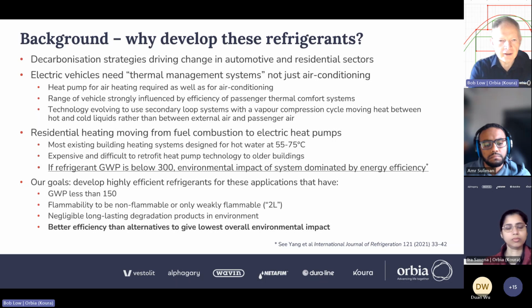So our refrigerant design goals then are really to design highly efficient refrigerants, where we're looking at GWP lower than 150. Flammability, we're focusing on non-flammable fluids. This is particularly appropriate for larger scale applications, such as some of the refrigeration type applications or building scale heat pump systems, where the constraints on using flammable refrigerants are challenging in terms of bringing refrigerant into the building, or weakly flammable refrigerants, the so-called 2L flammability, where the flammability can be managed quite easily by charge control and relatively inexpensive flammability mitigation around the equipment. Another design principle is we don't want anything to last a long time in the environment if the refrigerant gets out, so we want the breakdown products to be benign. And last but very much not least, better efficiency, because we're really focusing on environmental impact here.